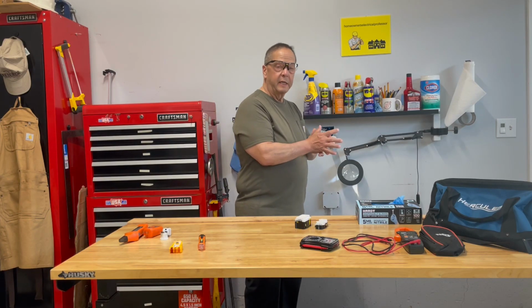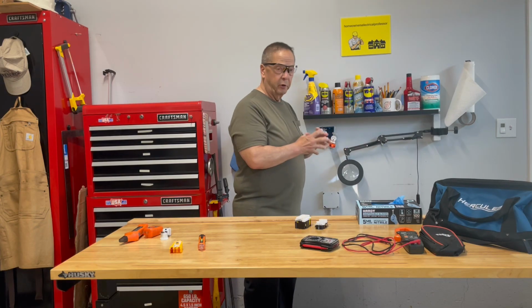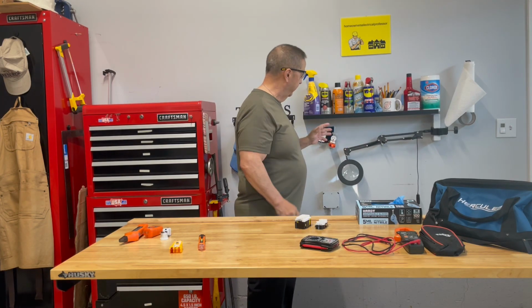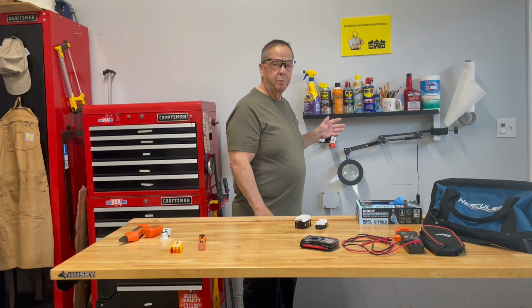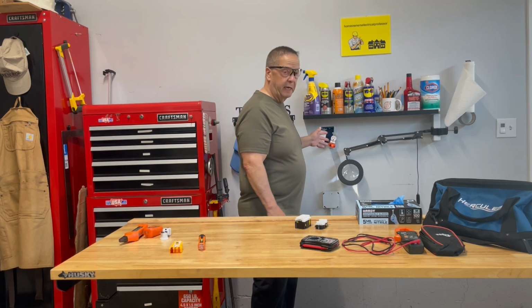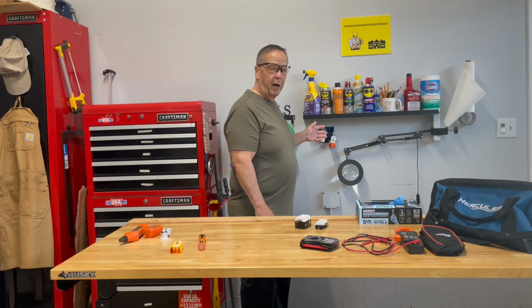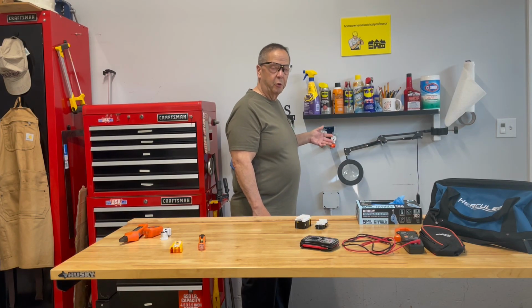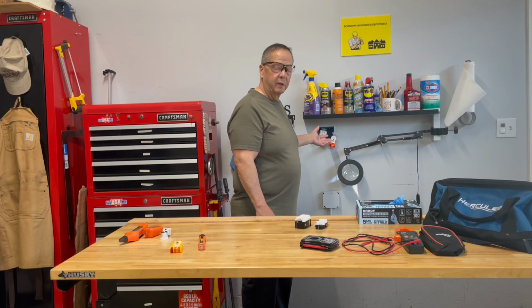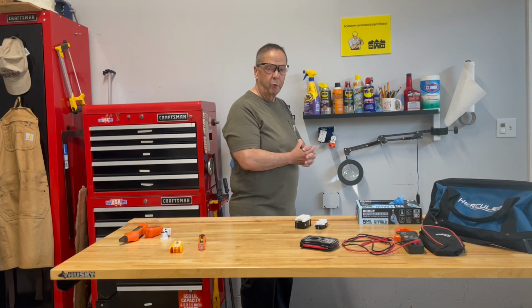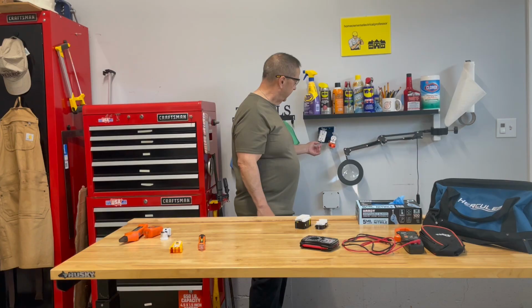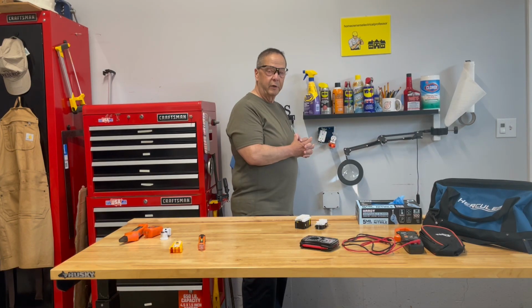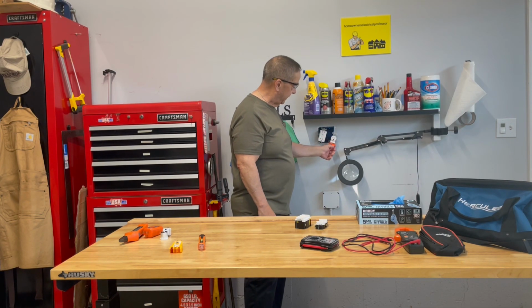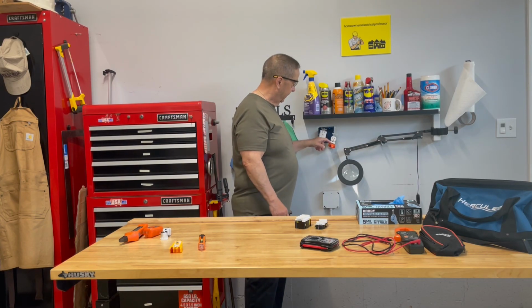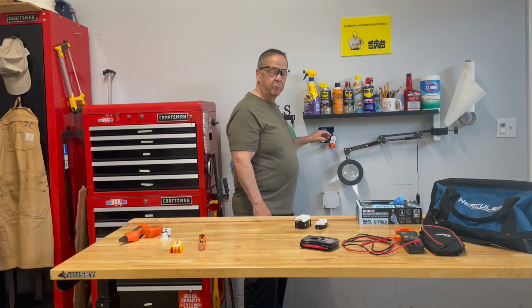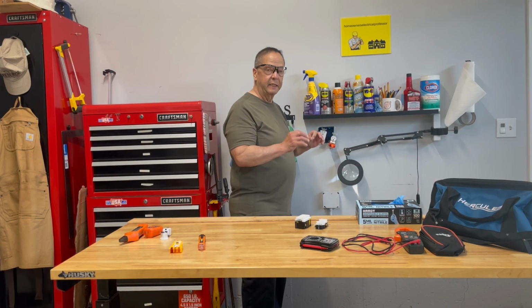Okay, now I went down to my electrical panel. I turned off the circuit. I came up here, and I do not advise anybody, since you're just basically students learning, do not attempt this at home, okay? Opening up a box after the electricity's been turned off and then turning it back on with live electric here, but I've been doing this for quite a while. Anyway, I disconnected the grounding or the green or bare wire, and as you can see now, my tester only has one light lit. And if you look on it, look at the chart, that light will tell you you have an open grounding connection.